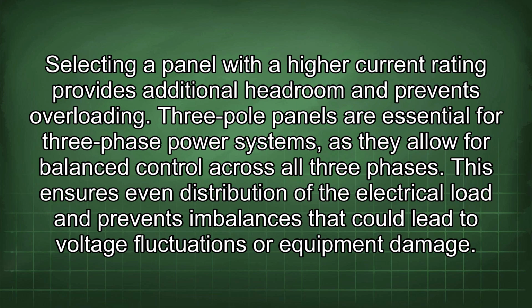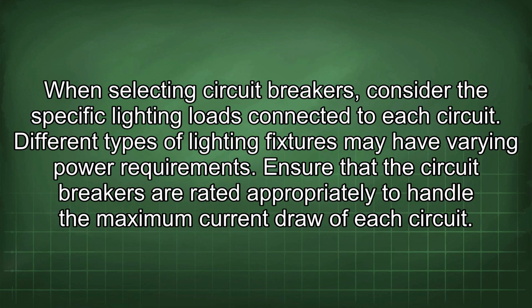This ensures the even distribution of the electrical load and prevents imbalances that could lead to voltage fluctuations or equipment damage. When selecting circuit breakers, consider the specific lighting loads connected to each circuit. Different types of lighting fixtures may have varying power requirements. Ensure that the circuit breakers are rated appropriately to handle the maximum current draw of each circuit.